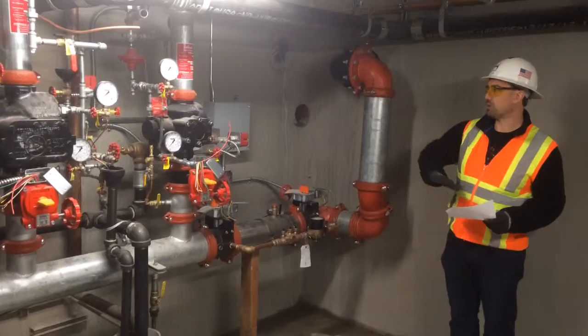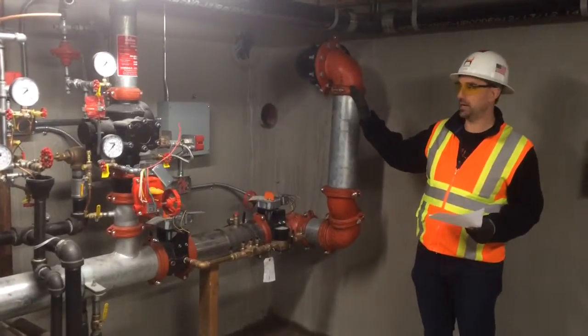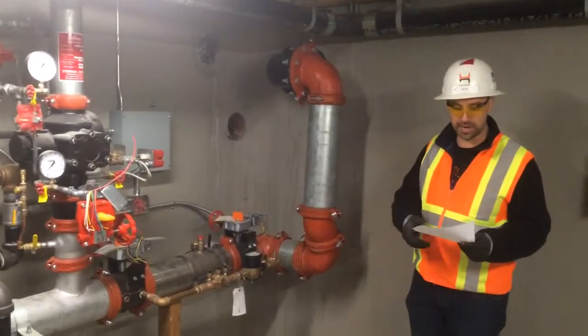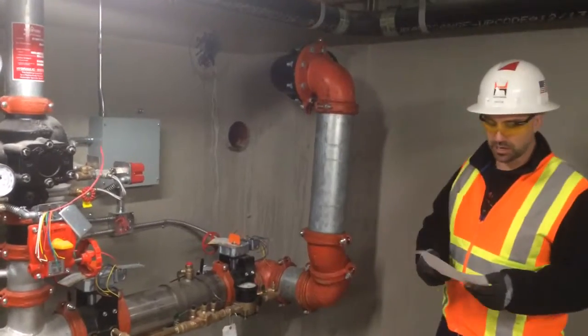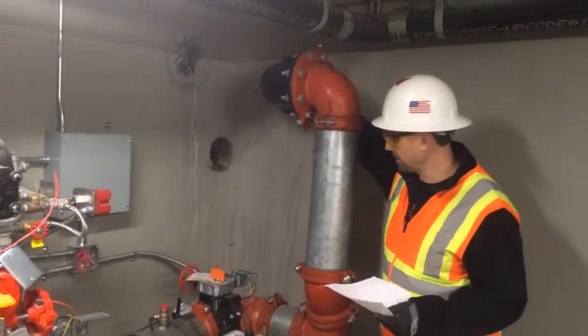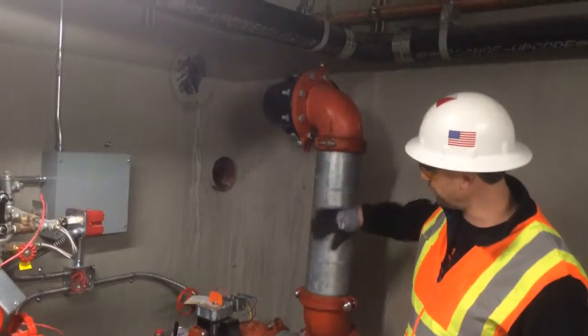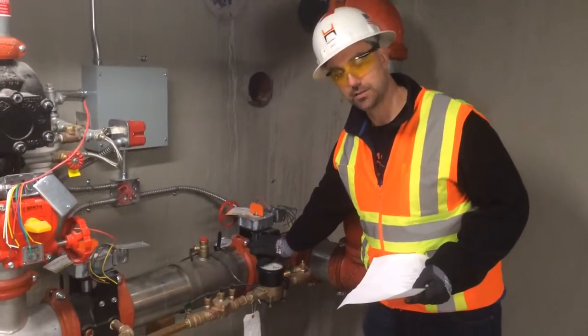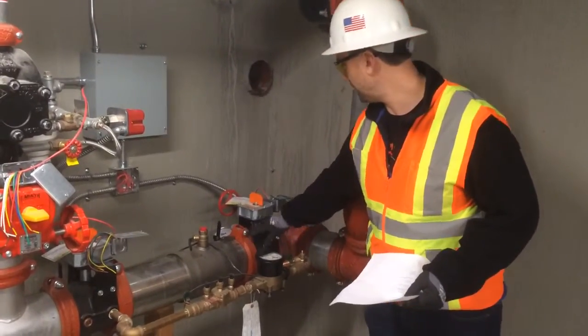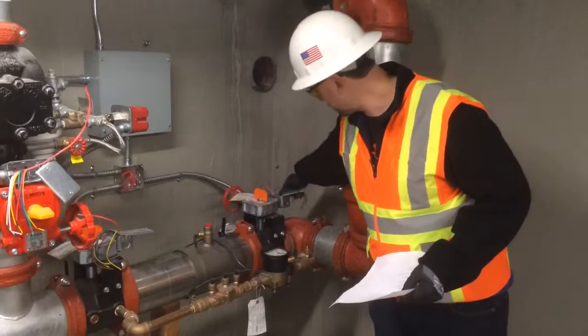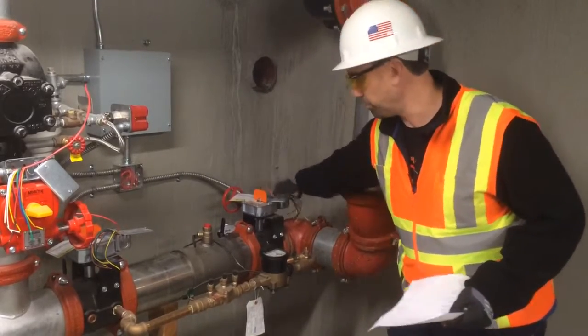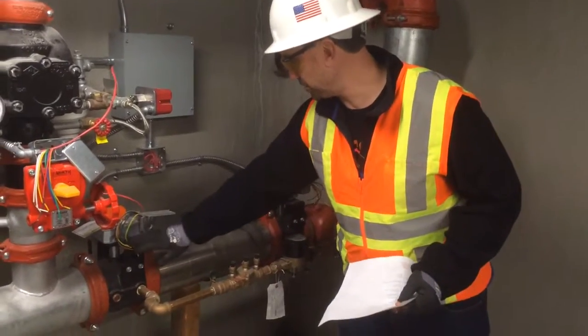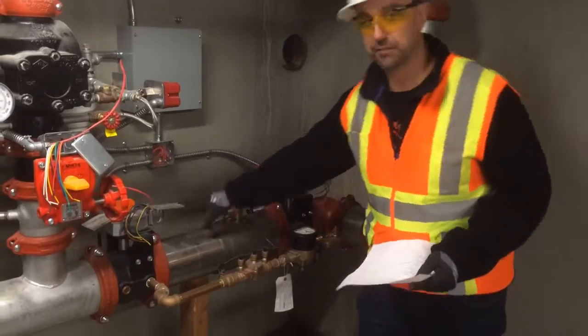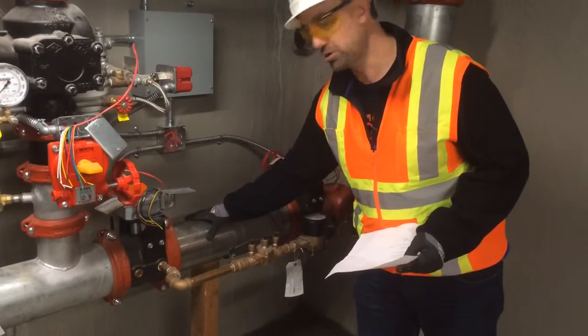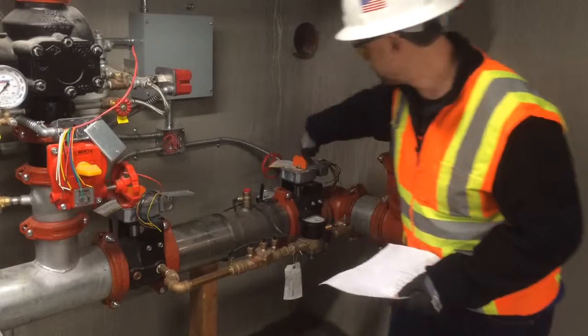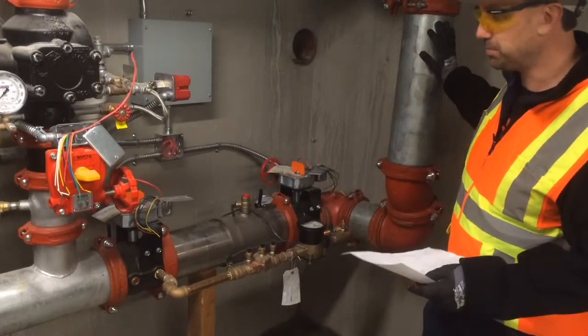This is the dry sprinkler system. It's compatible with a regular sprinkler system, and a lot of it has the same attributes. It all has a water supply. This water supply will come to an isolation valve. This isolation valve will always have a tamper switch. So this tamper switch is on both sides because it'll have an isolation valve on both sides. This system will have backflow prevention. That's this item here, and it stops the water from going backwards and contaminating the domestic water supply.